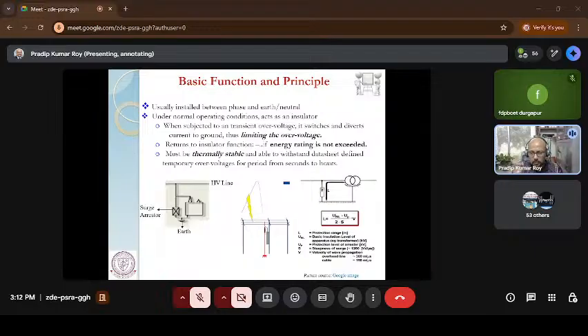Now, during the surge, it is found that the temperature can go to around 120 to 140 degrees Celsius. So if the temperature is not dissipated properly, sometimes the performance of the surge arrestor deteriorates. In that case, the devices or equipment should be thermally stable, and there should be some provision to dissipate that heat immediately after the surge goes back.